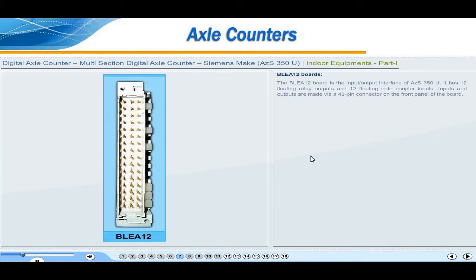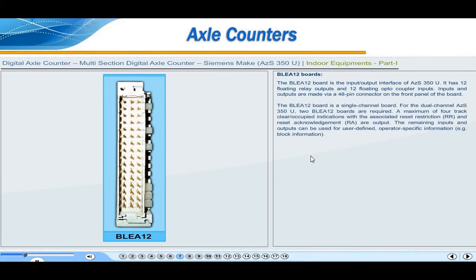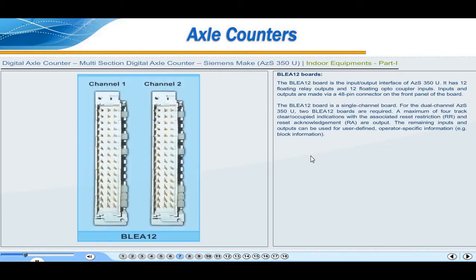BLEA12 boards. The BLEA12 board is the input or output interface of AZS 350U. It has 12 floating relay outputs and 12 floating opto-coupler inputs. Inputs and outputs are made via a 48-pin connector on the front panel of the board. The BLEA12 board is a single-channel board. For the dual-channel AZS 350U, 2 BLEA12 boards are required.